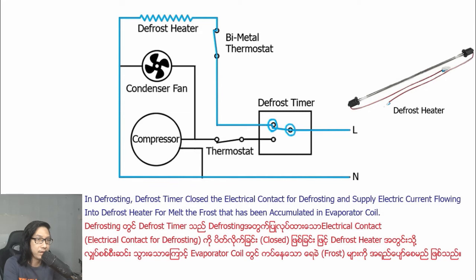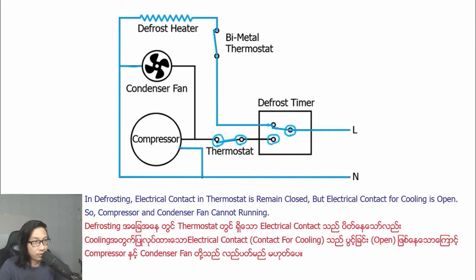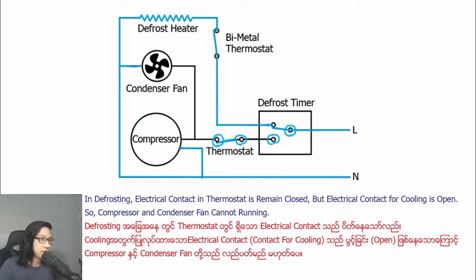The frost that has accumulated in the evaporator coil is melted. During defrosting, the electrical contact in the bimetal thermostat remains closed, but the electrical contact for cooling is open, so the compressor and condenser fan cannot run.